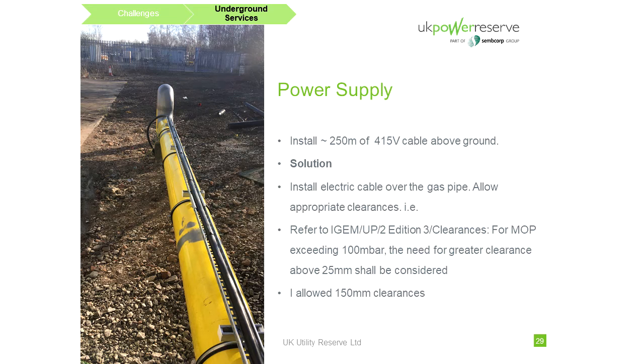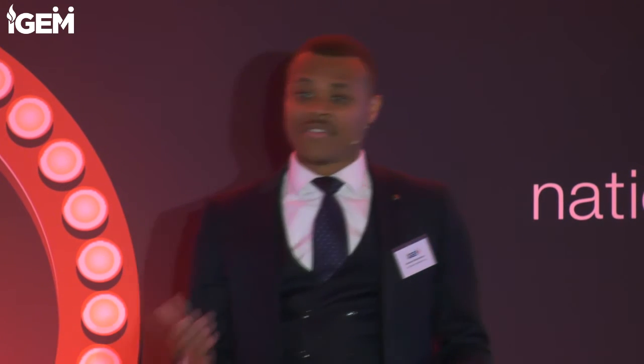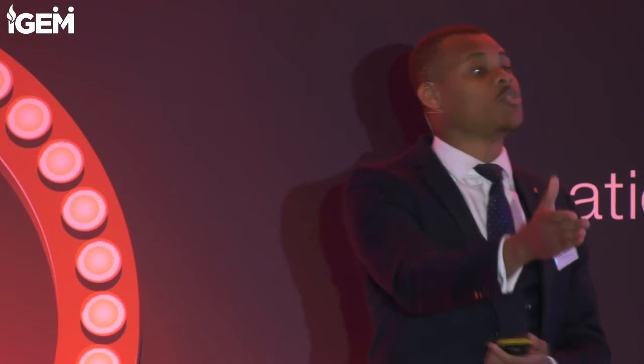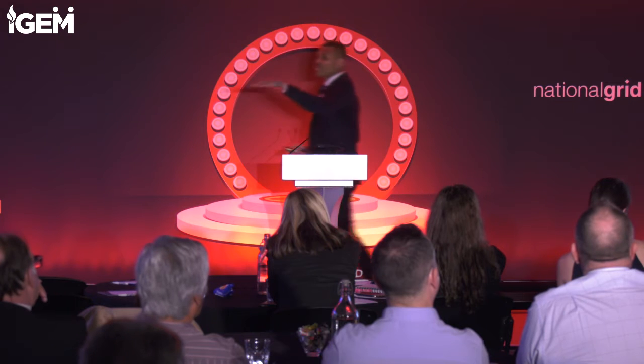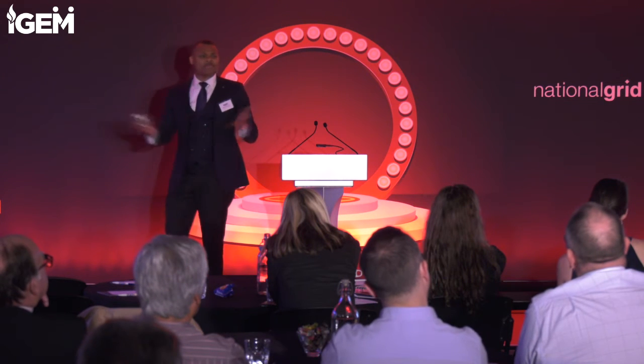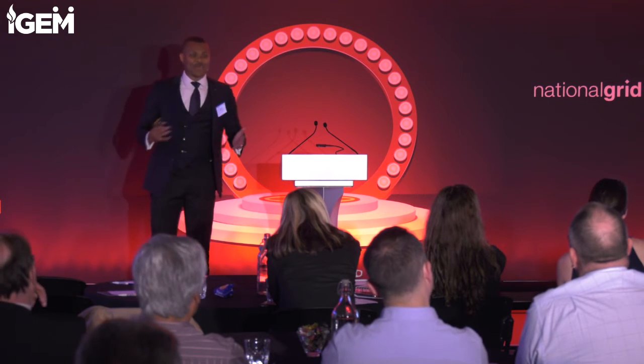So for the installation of the power supply, I said we're going to install the gas pipe on steel and basically install it above ground still. However, I've got issues with how to install the LV cable, because if I have to go above ground, installing that is going to increase the cost, because I basically have to install it on a cable tray, which increases the cost and affects my budget. So what I was thinking was, why can't we install this over the gas pipe? But basic knowledge says, why are you going to install an LV cable over a gas pipe?